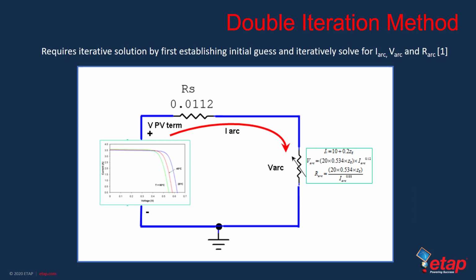However, this only occurs during normal operating conditions, as the voltage of the photovoltaic system nears the rated inverter operating voltage. Under arc flash or short circuit conditions, the effect of the maximum power point tracker controller is actually negligible, and the short circuit current is ruled by the irradiance IV or PV curves for the panel. It is perhaps here where the greatest mistake was made, in assuming that the DC arc flash in photovoltaic systems operates under this knee point or the maximum power point. And this causes the results to be overly conservative. To assume that the photovoltaic system operates constantly at the maximum power point during an actual arc flash event is not the correct way of looking at this.